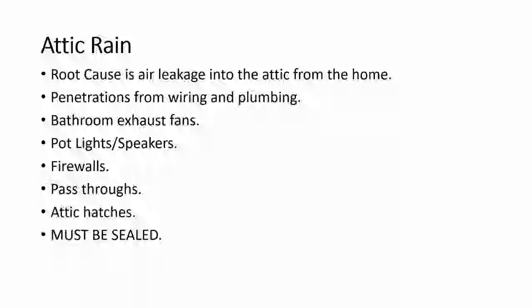So causes of this that I'm seeing, it's many-fold, but the root cause I feel is penetrations or air leakage from penetrations. Can come from wiring and plumbing. Bathroom exhaust fans are a real bad one for this. Pot lights and speakers. Firewalls, if we're dealing with a condominium type of a situation. Pass-throughs, essentially holes in the building structure that allow air and heat to come up from the home. Attic accesses. And the secret to fixing this, of course, is to seal those up.